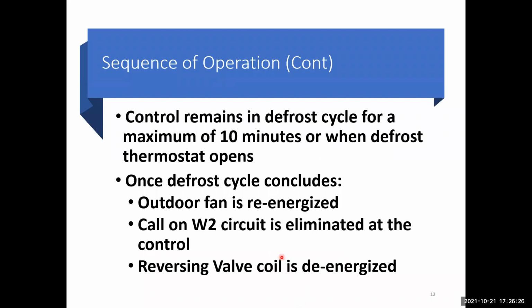Control remains in defrost for a maximum of 10 minutes, or when the defrost thermostat opens. Once the defrost cycle concludes, the outdoor fan is re-energized. Call on W2 circuit is eliminated at the control, and the reversing valve is de-energized.